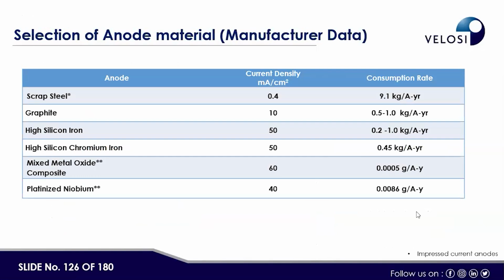We can also use scrap steel, the same old pipe which is in your store, as an anode material. But this will be diminished very soon, because for 1 ampere current, 10 kilograms of the pipe will be consumed, meaning you need to replace that anode bed very often and very frequently.